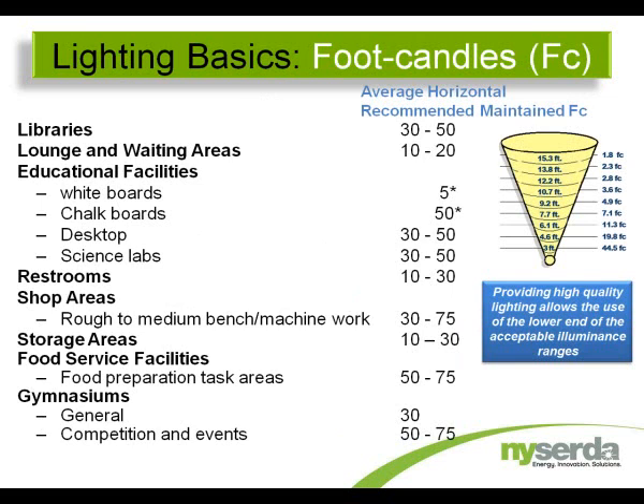To continue with foot candles, there are average horizontal recommended maintained foot candles for specific areas and space types. This is a quick example of a couple space types you might find within your school district and their average recommended maintained foot candles. Also note the foot candle drops the further you move from the light source, and the distance from the light source to the area you're shining light on will also change the level. Recommended lighting at a desktop is 30 to 50 foot candles, and science labs also 30 to 50, compared to your shop area where you want closer to 30 to 75, as students may be using heavy machinery or equipment and you want better illumination levels there.